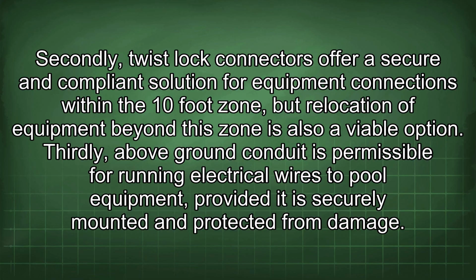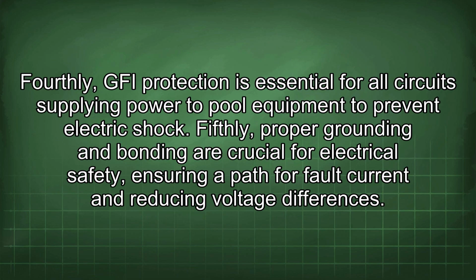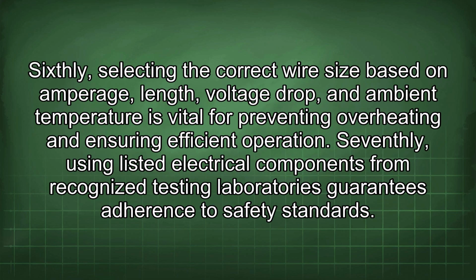Thirdly, above-ground conduit is permissible for running electrical wires to pool equipment, provided it is securely mounted and protected from damage. Fourthly, GFI protection is essential for all circuits supplying power to pool equipment to prevent electric shock. Fifthly, proper grounding and bonding are crucial for electrical safety, ensuring a path for fault current and reducing voltage differences. Sixthly, selecting the correct wire size based on amperage, length, voltage drop, and ambient temperature is vital for preventing overheating and ensuring efficient operation. Seventhly, using listed electrical components from recognized testing laboratories guarantees adherence to safety standards.